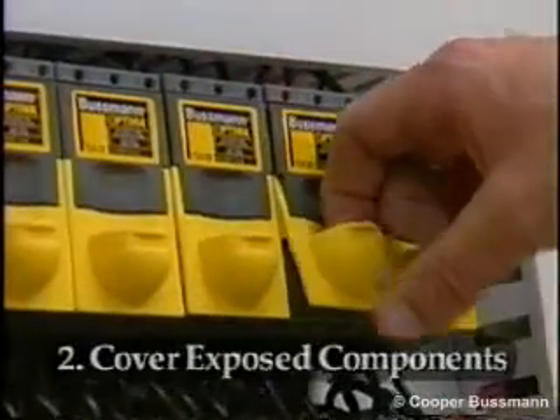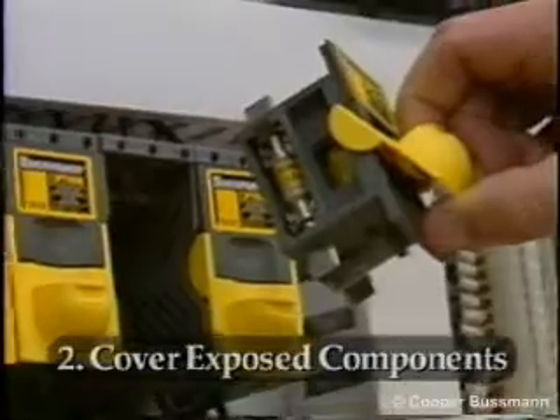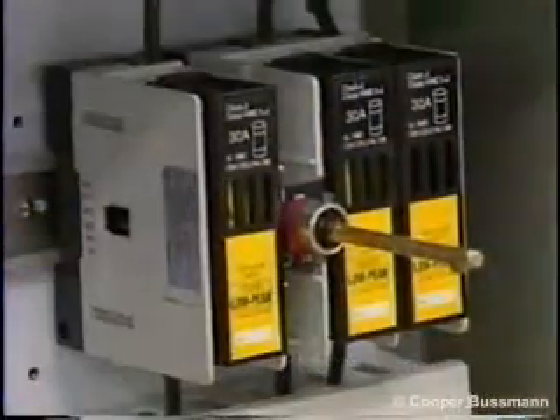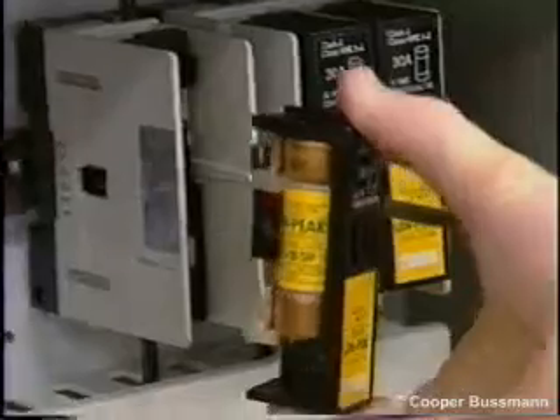An orderly system shutdown should also be required to minimize the hazards to personnel and equipment resulting from an electrical event. To address this situation, the National Electrical Code provides for a system of coordinated overcurrent protection devices. Cover exposed components. Equipment must be finger safe to avoid potential contact with energized conductors. It is not always possible to de-energize the equipment before working on it. If energized metal components could be exposed during routine maintenance, covers, shields, and insulating barriers must be used in accordance with safety standards.